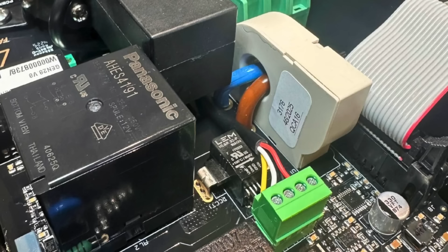Safety-wise, there's pen fault protection on board and an internal 6mA DC detector, and the RCD is set to trip at 20mA AC fault current, meaning for small faults it will trip the internal RCD before any external 30mA RCD. The idea being it will trip the charger before taking out the whole house.